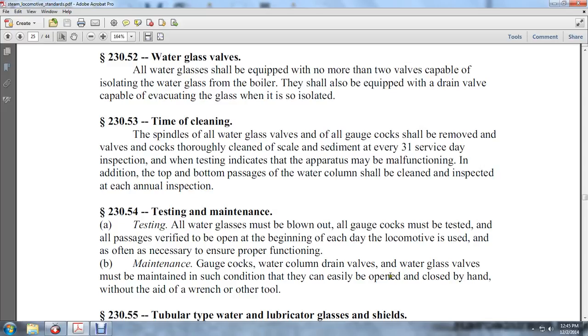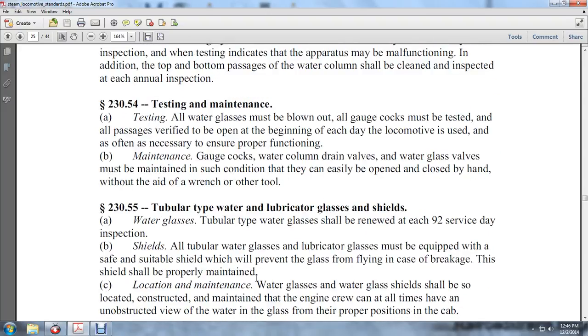Maintenance: Gauge cocks, water column drain valves, and water glass valves must be maintained in such condition that they can easily be opened and closed by hand without a wrench or other tool. 230-55: Tubular water glass renewal. Tubular type water glasses shall be renewed at each 92 service day inspection.